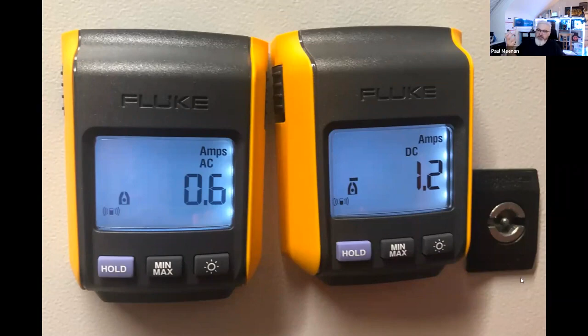I like to go around with clamp meters, everybody knows I do, and occasionally you pick up some weird stuff. There are documents for the railways - if you live within 60 meters you can get transients. This is just some clamp meter readings I've taken: I've got 600 milliamps of AC, but 1.2 amps of DC on the same cable. So what is floating around these networks? 1.2 amps DC is enough to blind any RCD anywhere. So again, moving on, but it's worth experimenting - these clamp meters can really start educating you about the performance and behaviors of a connected system.